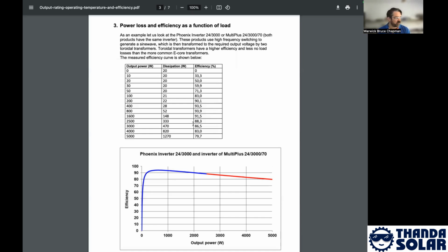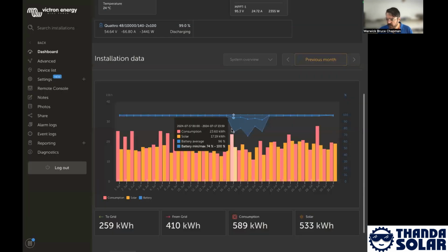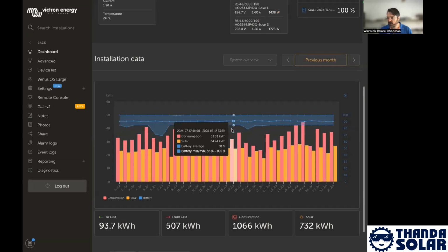But where systems are operating completely off-grid, or where they aren't feeding into the grid, and the nominal or average power consumption is much lower, we should see those losses being even less. And I'll try and find a site that's a good example of that for us to have a look at. So if we go back here, we understand this particular site is feeding into the grid. And as we saw there, it had a 17.8% loss. Let's have a look at a multi-RS site.